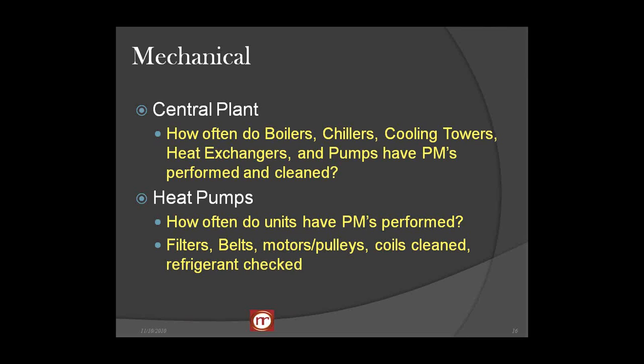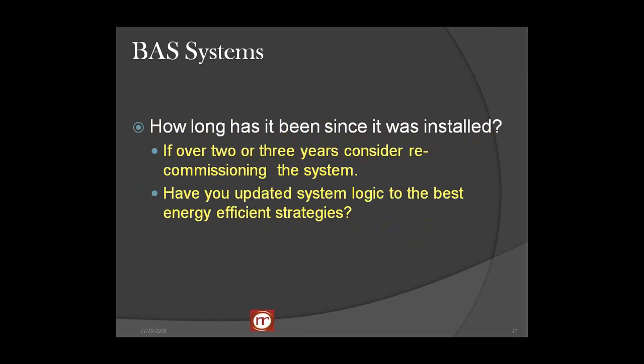You need to occasionally check the refrigerants as well as the filters and cleaning coils. Did you know that a dirty filter or a dirty coil that is stopped up can reduce the efficiency of a piece of equipment by as much as 20 to 30%? Now, you have a building that has a design degree which says that at X amount of temperature we can deliver a comfort level, and that's at 100%. Well, if I've lost 20%, I only have 80% because today I'm above design conditions and I can't do it. I can't heat or cool it. So it's important that you clean the coils and change the filters.